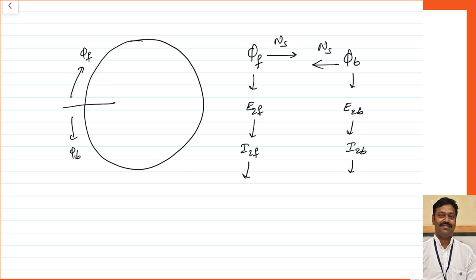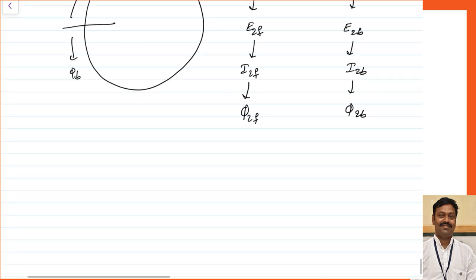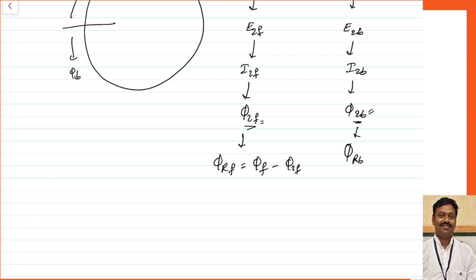Because of the rotor currents, fluxes phi_2f (forward) and phi_2b (backward) are produced by the rotor. These two fluxes are in opposite directions and will always try to oppose their cause. The cause is the main field flux: phi_f is responsible for phi_2f and phi_b is responsible for phi_2b. So the resultant forward flux in the air gap equals phi_f minus phi_2f, and the resultant backward flux equals phi_b minus phi_2b. The forward resultant produces forward torque and the backward resultant produces backward torque.